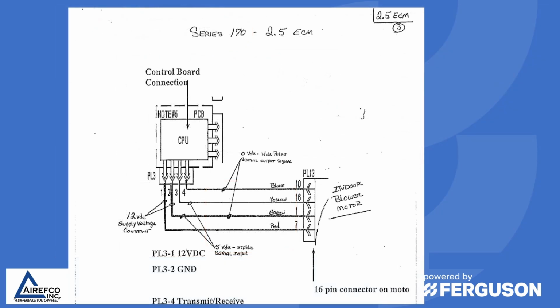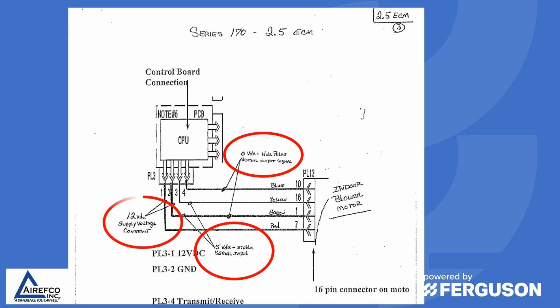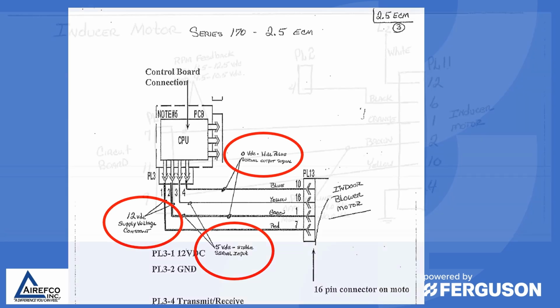Here we have a graphic of one of the newer motors that has a 4-pin connection for the communication. And you'll notice that between the blue and the green, you should have 0 volts DC, and that will pulse with the serial output signal as the motor is commanded to run. Then you have a 5 volt DC stable serial input between the yellow and the green. And then you have the 12 volts DC supply voltage that is constant between the green and the red.